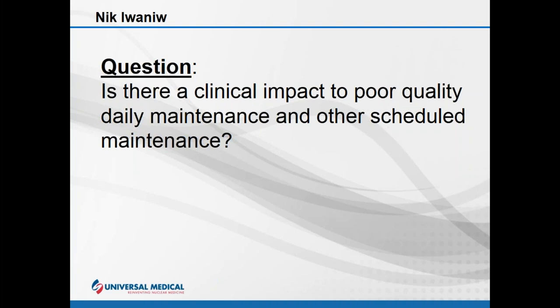Here's why: there's a couple of real-life scenarios of why we do this clinically and the importance in making a diagnosis. Craig mentioned the COR, or center of rotation, which is applied during SPECT studies. As the camera rotates around the patient to create an emission tomography, it has to accurately register where that camera is in order to create that SPECT study. If that COR is not accurate and not calibrated correctly, there can be defects created in the images, and some of these can be subtle, some not so subtle.